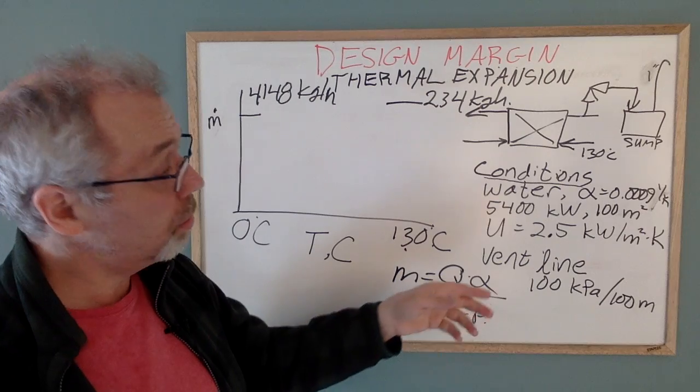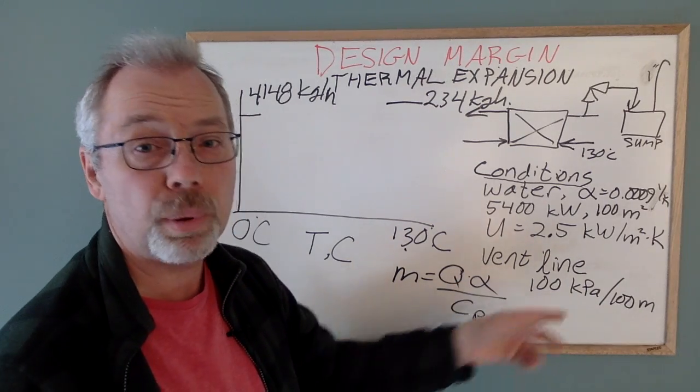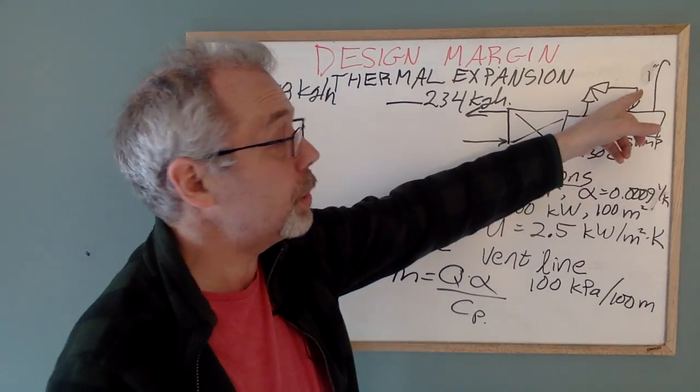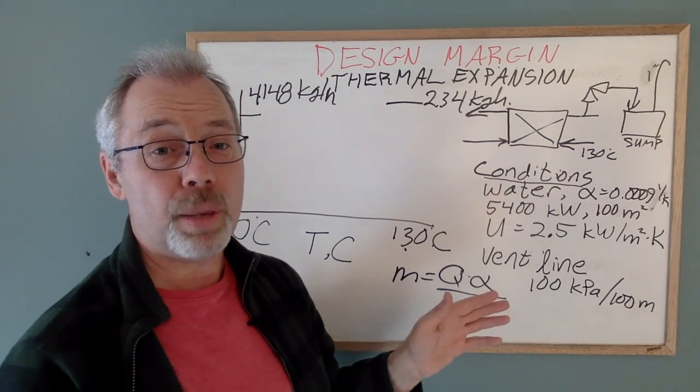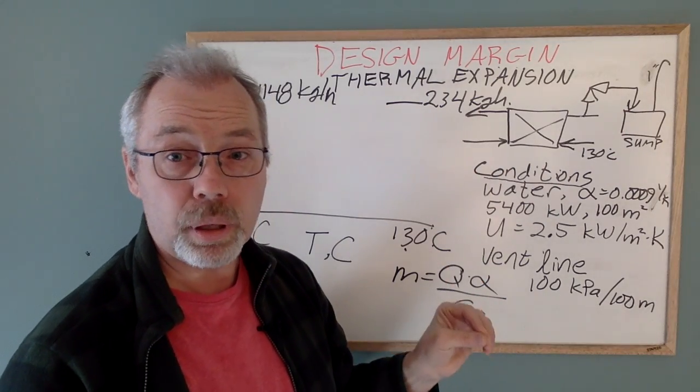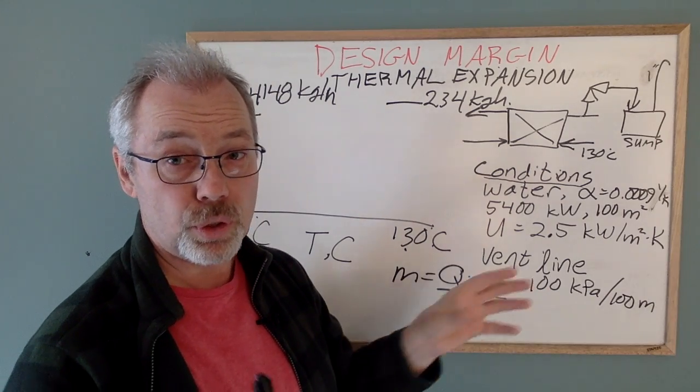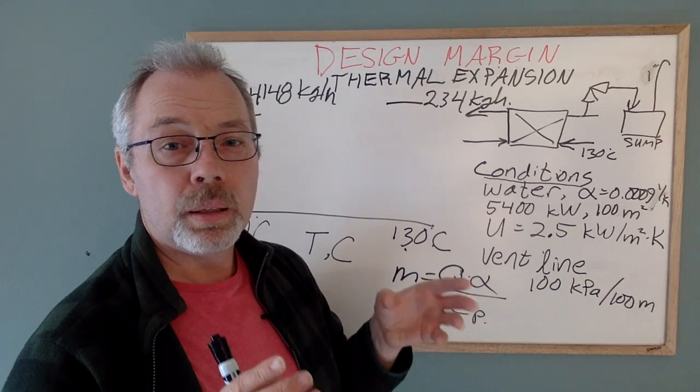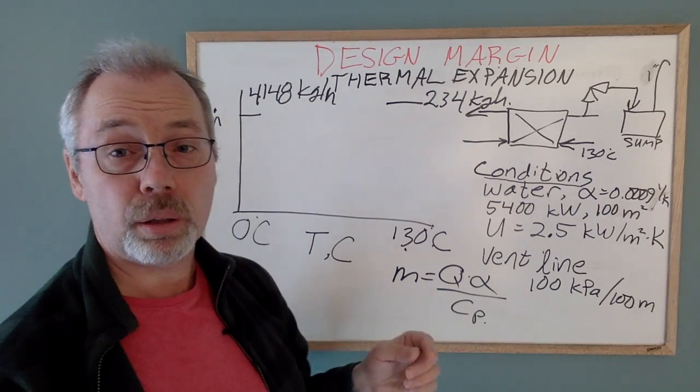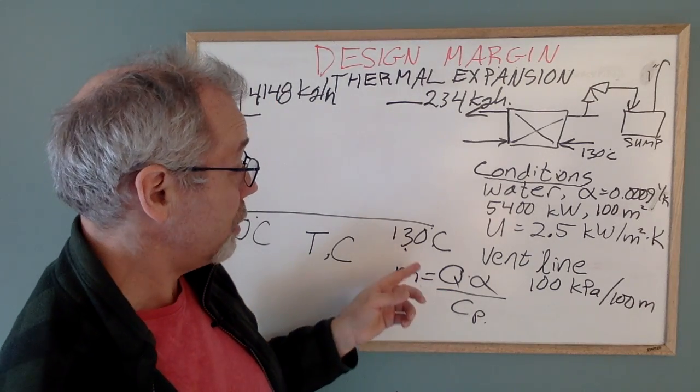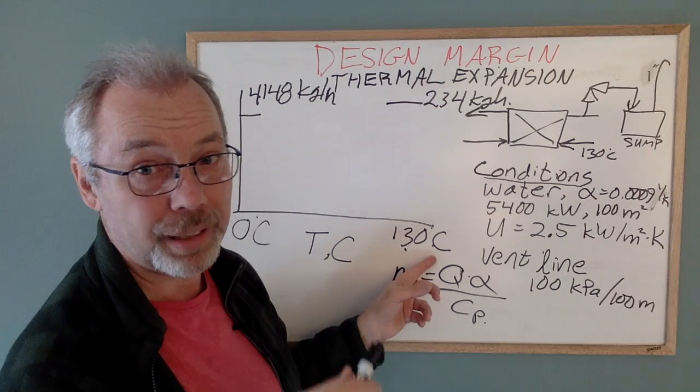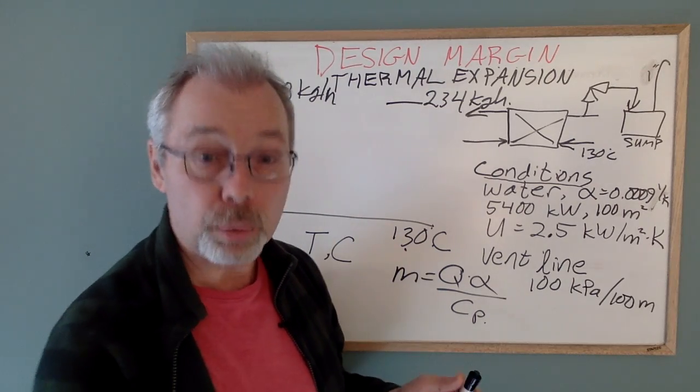Now, with our design criteria for hydraulics being 100 kPa per 100 meters, this means we need an inch and a half vent line. Our existing one inch line is too small. Now, this is where we need to step back and say, hold on, take a minute. This would require us to tie our PSV into the flare line with the construction risks associated with it. Is it possible to have the full relieving rate of over 4,000 kilograms an hour simultaneous with the highest temperature of 130 degrees Celsius? And the answer to that question is no. We need to look at this a little more carefully.